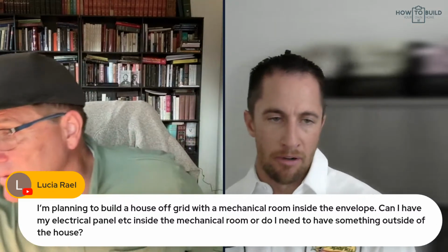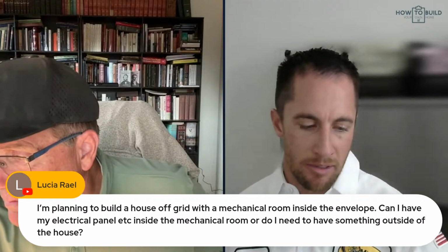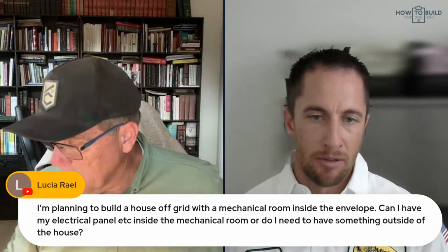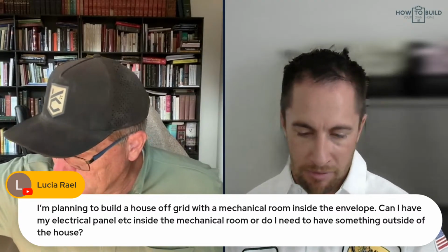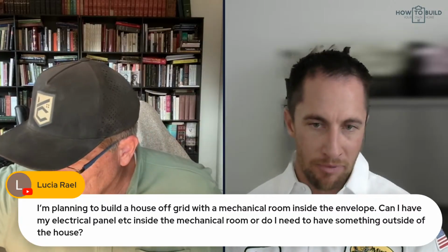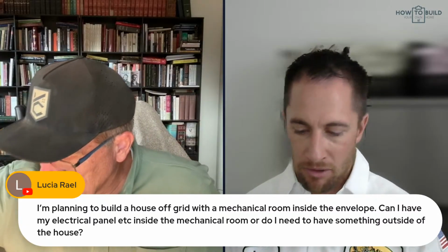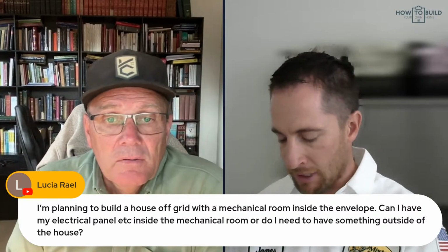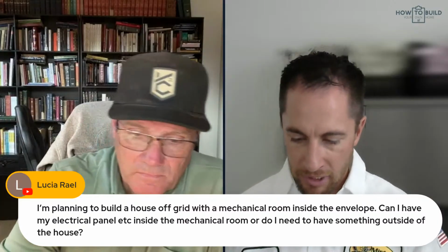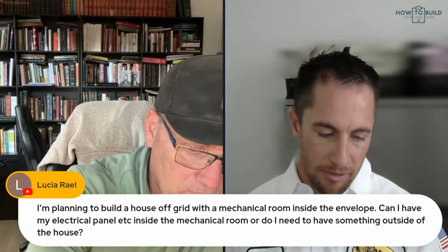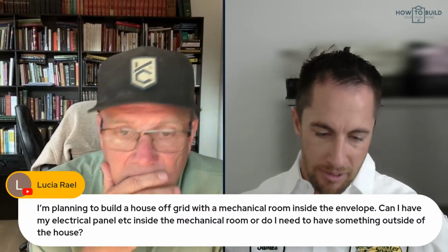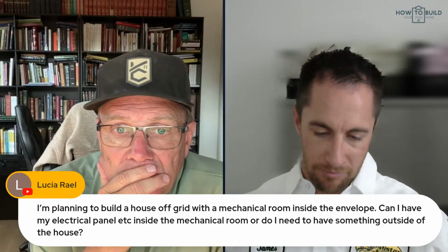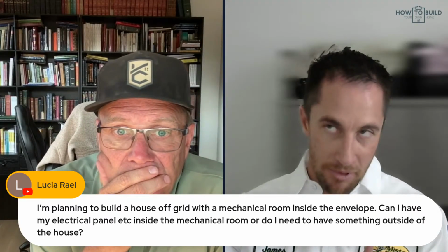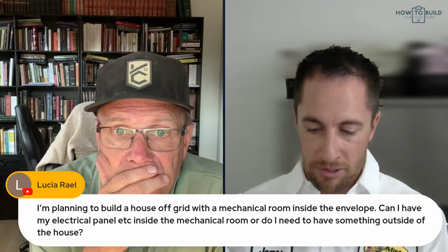You just have your service panel with a meter outside. You can definitely put your panel in that mechanical room — not a problem there. Or if it's a sub panel, if you have a lot of equipment in there, you can absolutely do that. The only big requirement when putting it in there is your clearances: you've got to have 30 inches of working space, and if I remember right, 30 or 36 inches in front of it.